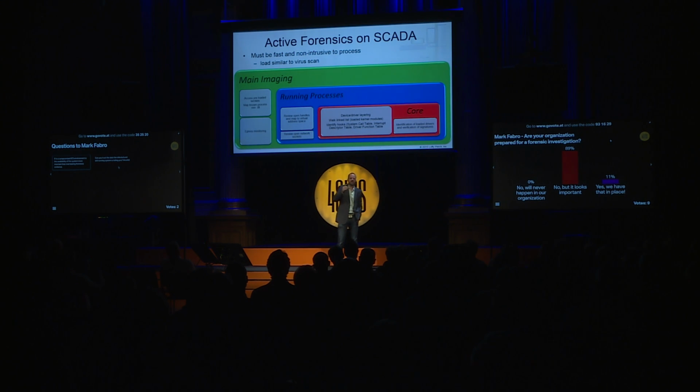It does require explicit understanding of the applications on the control system side, what the vendors are doing, and a specific technical understanding about the behavior of the applications, because you're doing a contrast and compare of the behavior you are observing in real time on the infected system versus what you should see on a non-infected system. The main imaging component is pretty straightforward because you're looking at the preloaded servlets and you're mapping the known executables and the libraries based on the actual authorized, legitimate functionality of the control system applications.